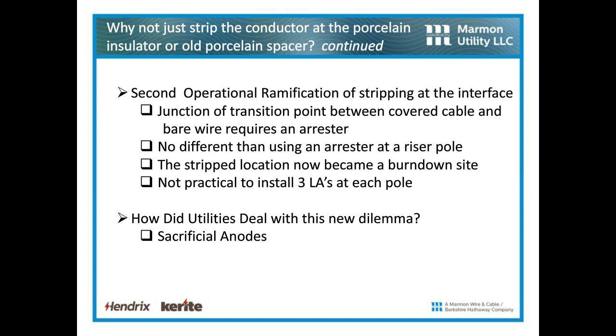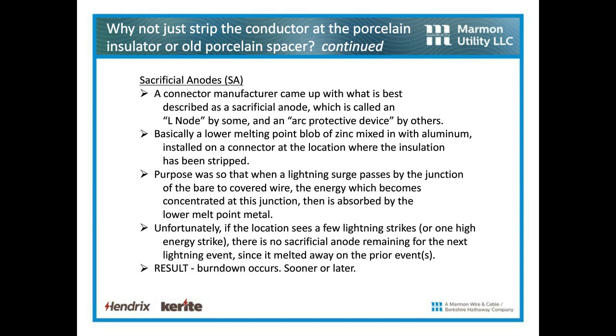Well, somebody came up with what's called a sacrificial anode. A sacrificial anode is essentially a lower melting point blob of zinc mixed in with aluminum, installed on a connector at the location where the insulation has been stripped. The purpose was that when a lightning surge passes by the junction of the bare to the covered wire at that insulator point, the energy which becomes concentrated at this junction is absorbed by the lower melting point material. Unfortunately, if the location sees a few lightning strikes or maybe a single high energy strike, there's so much sacrificial anode burn that there's none left remaining for the next lightning event. So the result is eventually I'm going to have a burn down.